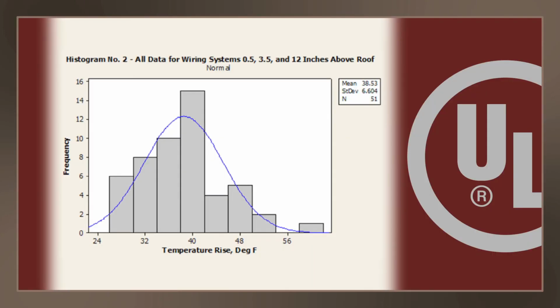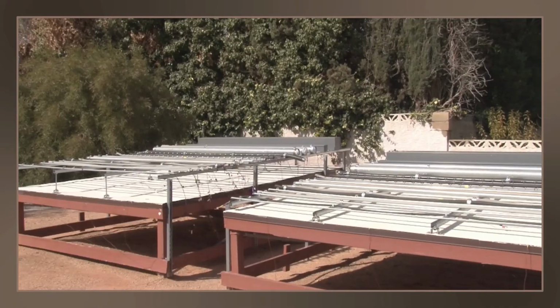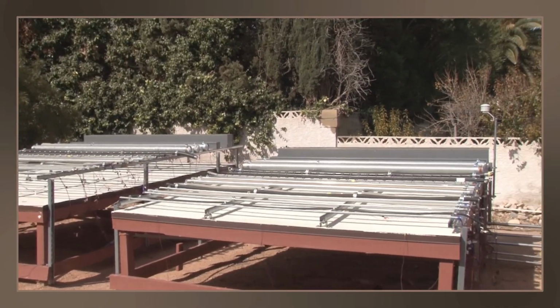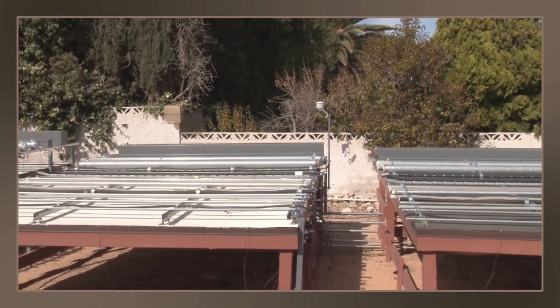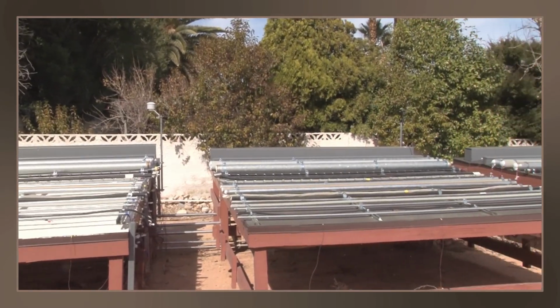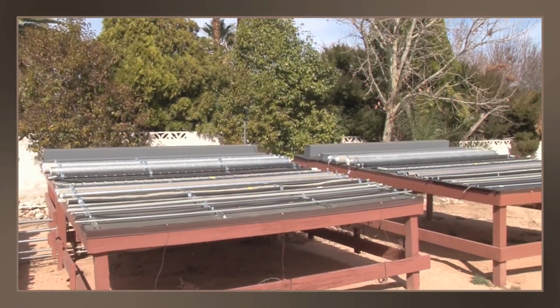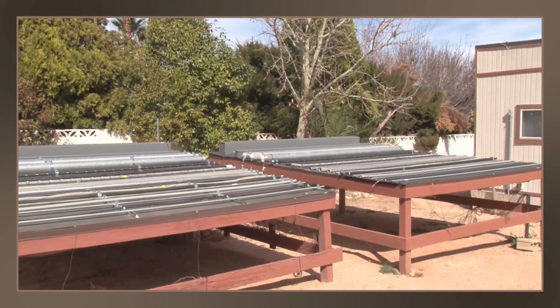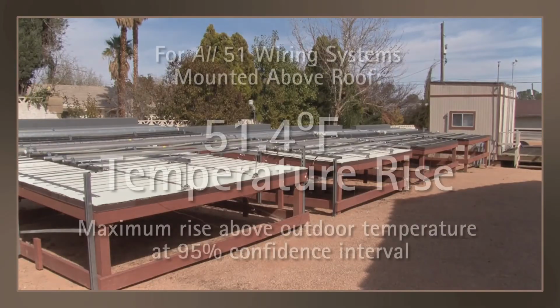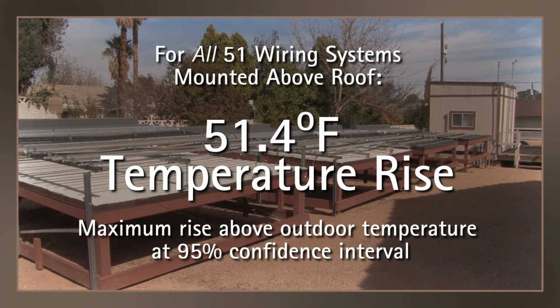This histogram shows the 90th percentile temperature rise data for all wiring systems mounted 1/2, 3.5, and 12 inches above the roof. For all 51 test samples of wiring systems mounted off the roof, the mean temperature rise was 38.5 degrees F, with a standard deviation of 6.6 degrees F. The maximum temperature rise for all wiring systems mounted off the roof with a 95% confidence interval would be 51.4 degrees F.